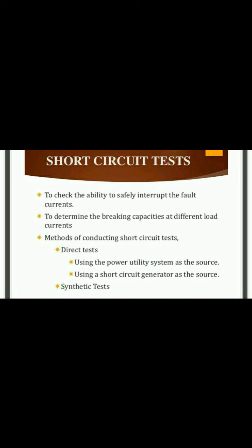The detailed interruption of a circuit breaker is carried out under these short circuit tests. These tests are very important in concern with a circuit breaker, because the breaking capacity of that particular circuit breaker depends on them, because breaking capacities at different load currents are determined under different conditions or values. So this is called a short circuit test of a circuit breaker.